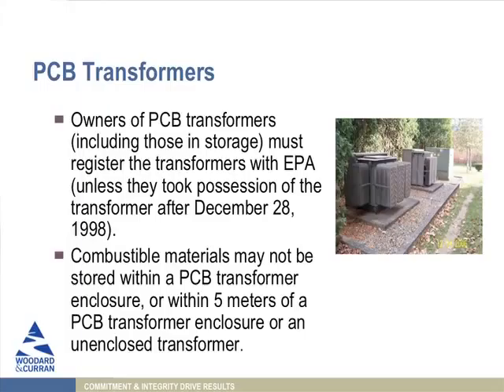One key thing you need to know is that if the campus has PCB transformers, they all had to be registered with the EPA as of 1998. So if you have a PCB transformer - meaning 500 parts per million or more concentration of PCBs - it had to be registered with the EPA by 1998. If you took possession after 1998, you're allowed to presume the prior owner registered them, though it's good to get a copy of that documentation. If your campus has PCB transformers above 500 parts per million, make sure they've been registered with the EPA.